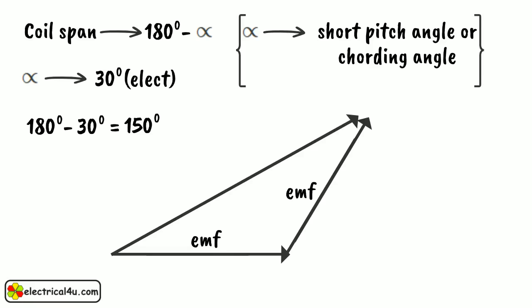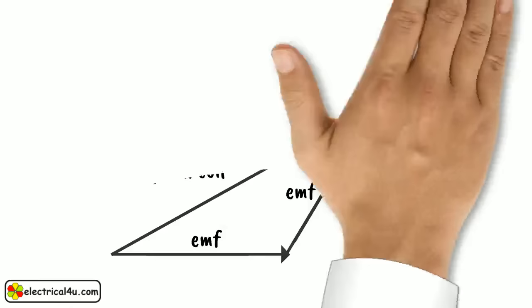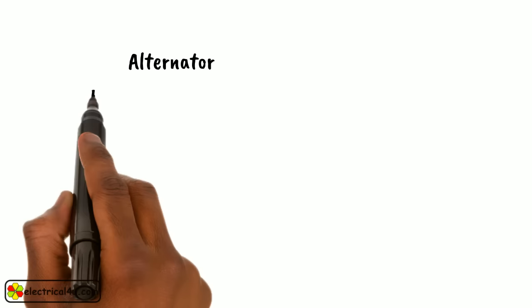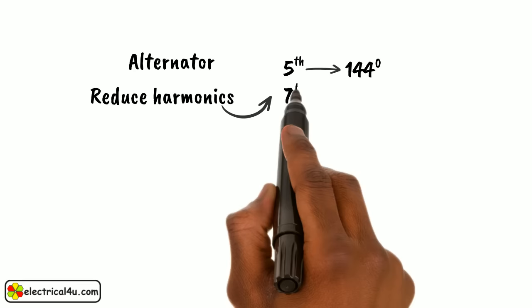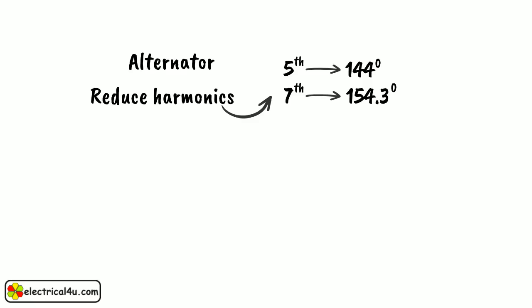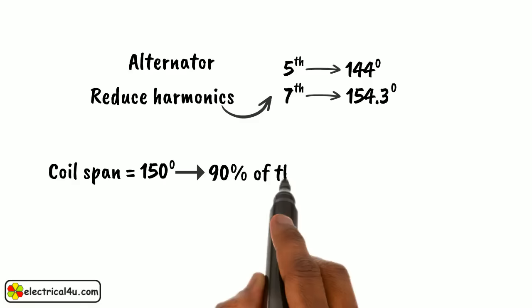In case of short pitch winding, the resultant EMF is the phasor sum of the two EMFs induced in the coil sides, and it is always less than the EMF induced in a full pitched coil. Short pitched winding is used in electrical machines, especially in alternators, to reduce harmonics. For example, to eliminate the 5th harmonic the coil span must be 144 degrees, and to eliminate the 7th harmonic the coil span must be 154.3 degrees. In modern alternators, the coil span is chosen as 150 degrees, such that nearly 90% of the 5th and 7th harmonics can be eliminated simultaneously.